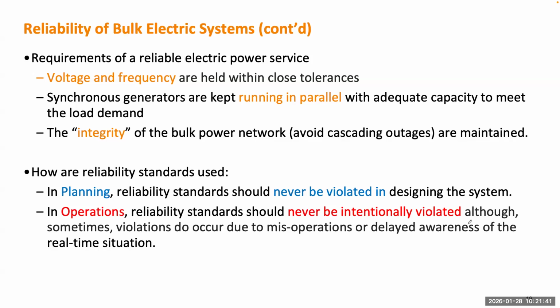Here we talk about the BES, bulk electric system, to be reliable. To address any reliability concerns, there will be two stages. First is the planning stage, which is before any event happens. The planning engineers need to design the reliability standards, such that if you follow the standard, the system should be fine for almost 100% likelihood, which means those standards should avoid any violation of reliability requirements. But in reality, when the system encounters a disturbance that has not been studied by planning engineers, the operator will try their best to follow all the existing standards, but there may still be some issues. So in reality, even if you meet the standard, the system may still be insecure, but you will try your best. You should not intentionally violate any standard.